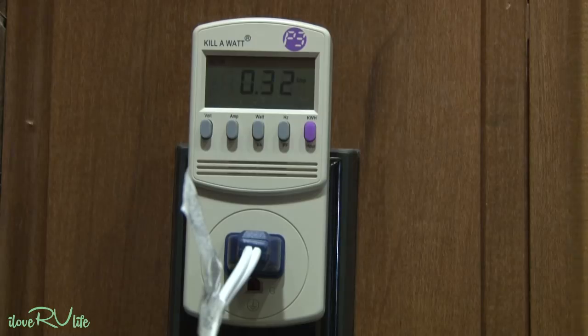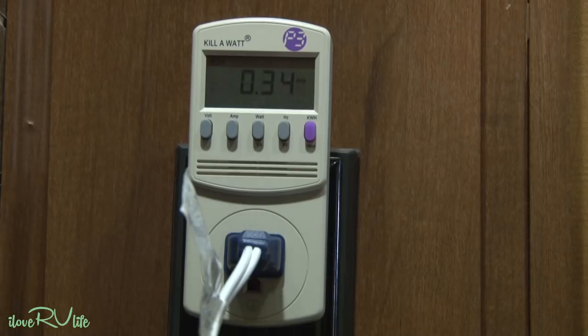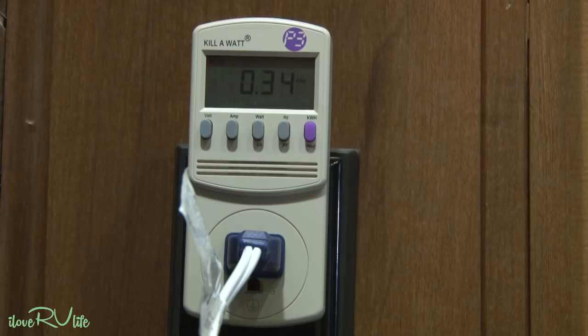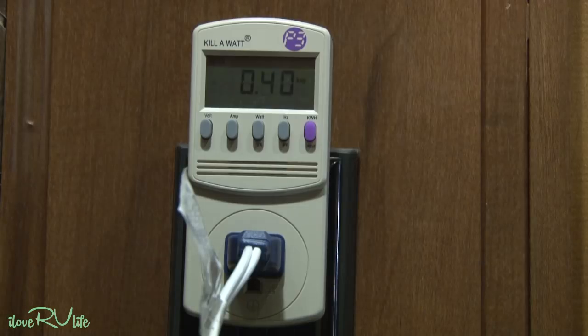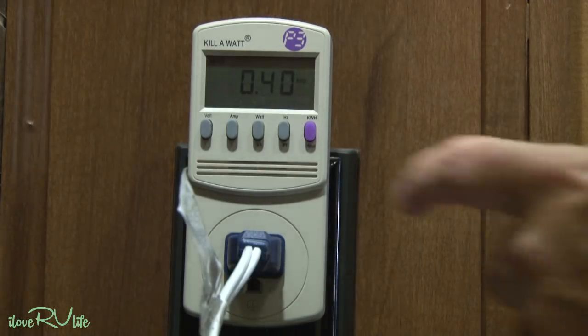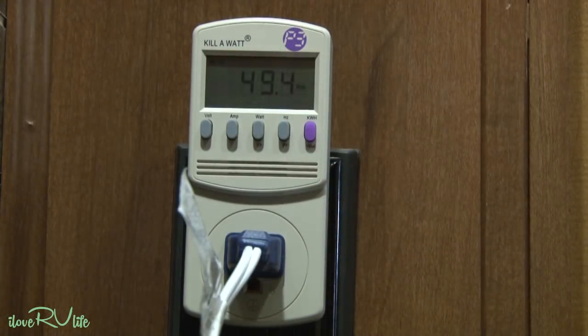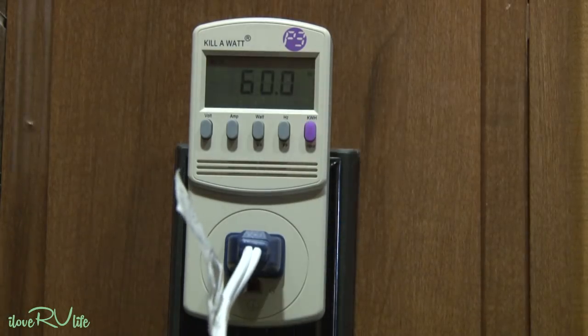Then I can step it up to the next speed and see that it doesn't pull that much more power - about 0.34 amps - so for a minimal increase in amperage budget, it's not taking a lot more power on the next setting. Then I'll put it on the highest fan setting - you can hear it running in the background - and it jumps up to 0.40, so 0.4 amps more, roughly 50 watts here. I can also check the hertz running outside the facility, and it's working absolutely great.